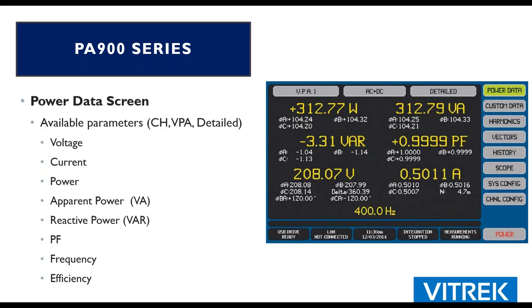The next couple of slides, I'm just going to go over some of the screens that we have available for being able to look at the data. The first screen is our power data screen. The parameters available are voltage, current, power, apparent power, reactive power, power factor, and frequency. In the upper left-hand portion of this screen it says VPA1. That will allow me to take a look and see efficiency measurements, so I could click on where it says VPA1 and get a drop down for efficiency. If I have my VPA set up properly, I'll be able to get my efficiency readings out of this as well, so that's the eighth parameter that can be viewed on this particular screen. There's also a lot of extra detail, so I have both AC and DC readings on here as well. That's my detailed screen.